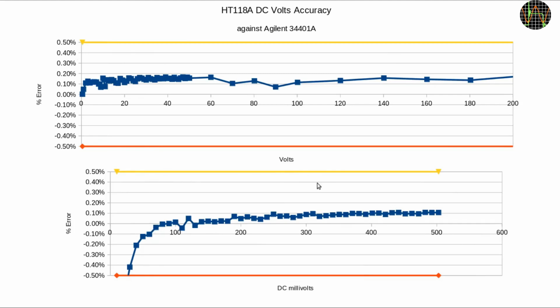They represent the specified accuracy for this range, so for example plus minus 0.5% in this case, making it easy to see how the measured accuracy of the HT118A fares against its specification. Quite well, as you can see. Since my remote controllable power supply is limited to 50 volts, I did the remaining parts by hand using a high voltage power supply, which is why there are far less data points.